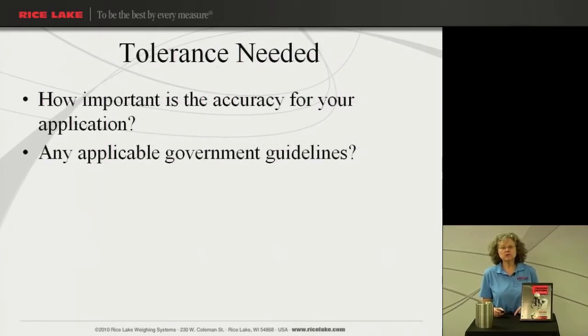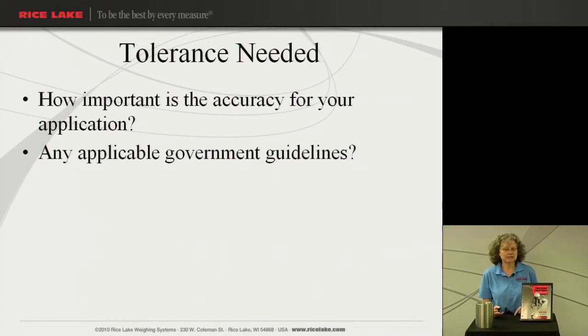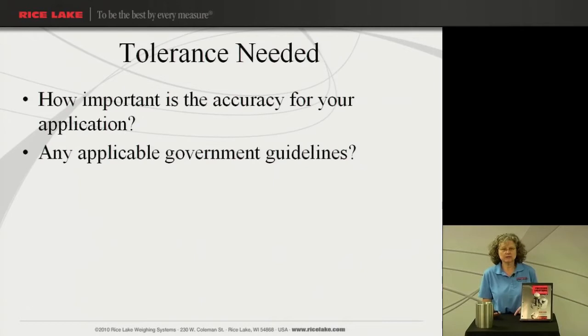What else might be important for the tolerance you'd be choosing? How important is the accuracy for your application, and are there any applicable government guidelines? Not only do you have requirements controlled by the government — referring to OIML, NIST, or ASTM — but there could also be other government or corporate guidelines that are important. For instance, if you're doing pharmaceutical work, you might need to refer to the FDA, or if you're doing transportation or work for state agencies, you might need to look at state requirements. You also need to look at the product itself: how accurate are your weighments? Are you weighing on a balance with a high resolution? Then you're going to need a weight with a better tolerance. The tolerance should be one-third to one-quarter the tolerance of the resolution of the balance.